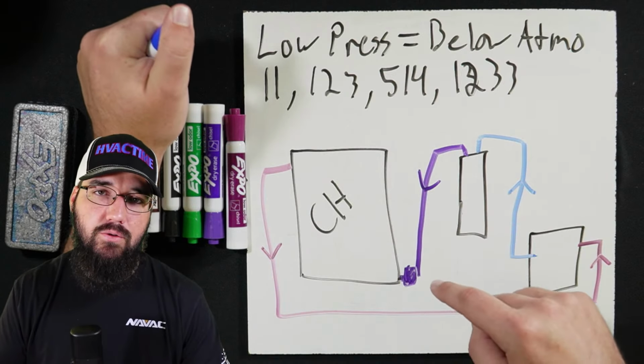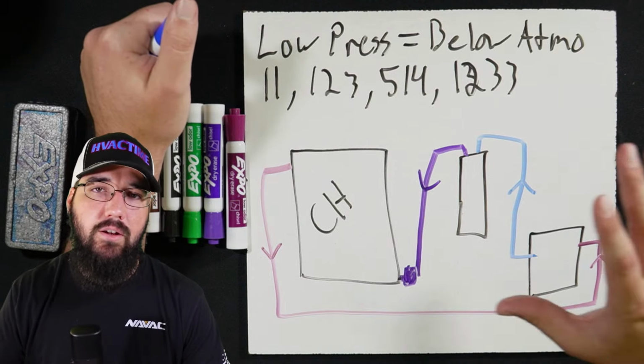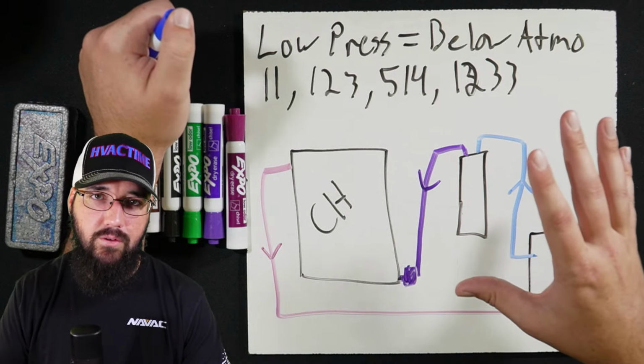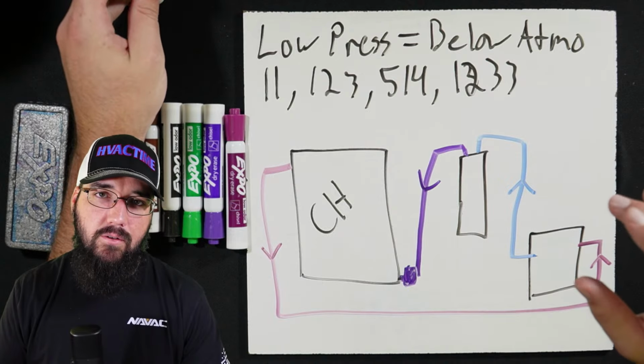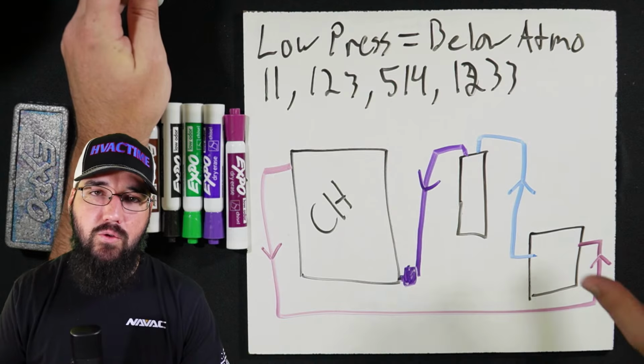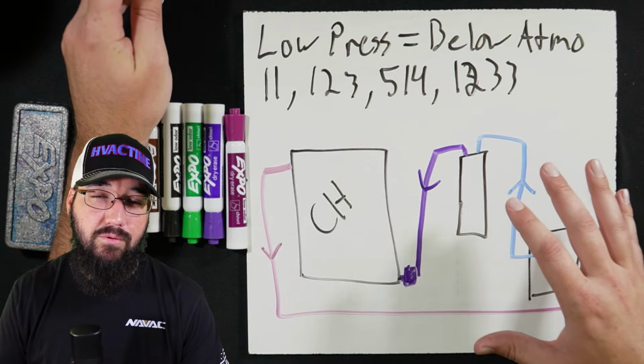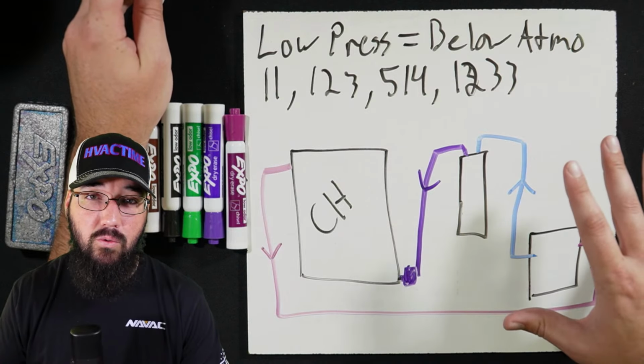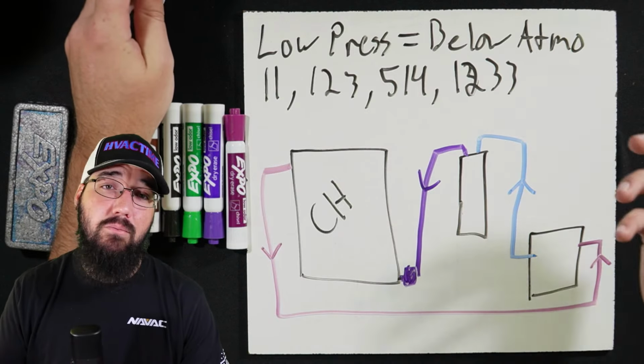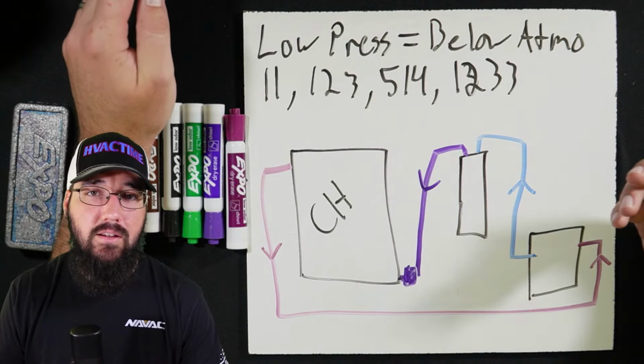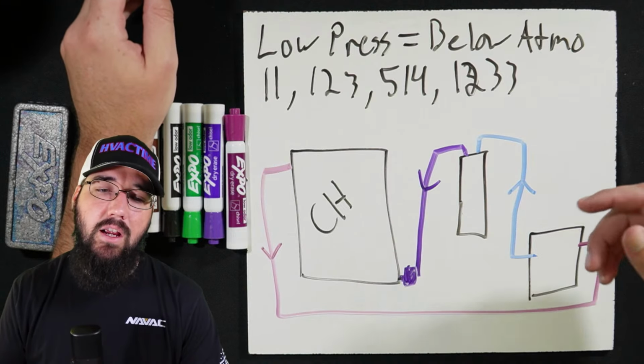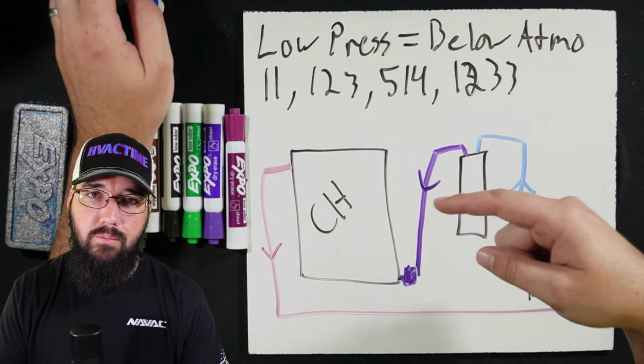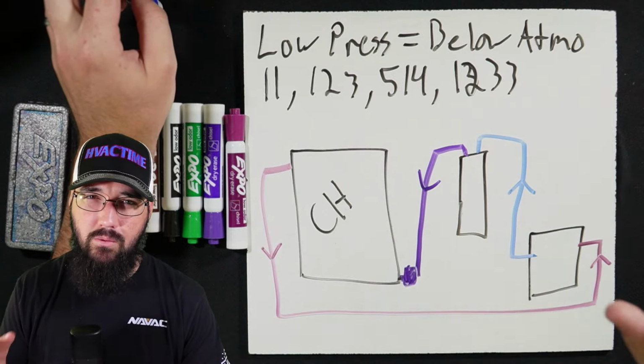But however the process you use, if we tried to do like a vapor charge, right? So that's one way to do this. Then trying to boil off, especially a low pressure refrigerant, it's already at such a low pressure, you've got to draw that tank down and boil all that refrigerant out. It's just not feasible, right? And then you could do a liquid pump transfer, right? So that would be one technical method.